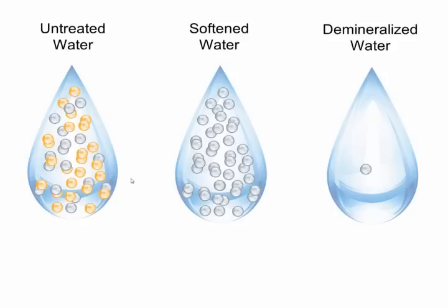Okay. So if you look at water, and this isn't a chemistry exam, but just looking at water from an untreated standpoint, basically water that has minerals, softened water, and demineralized water, what happens is these brown little particles indicate hard water, basically calcium and magnesium, and the blue would indicate any other type of mineral or salt. So untreated water has these. And as a result, left untreated, it will set up the effects of galvanic corrosion and limescale formation in your system.